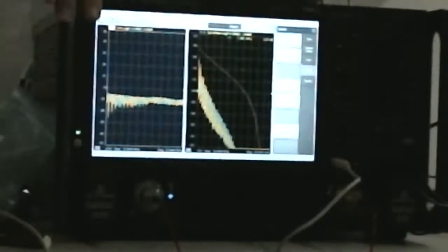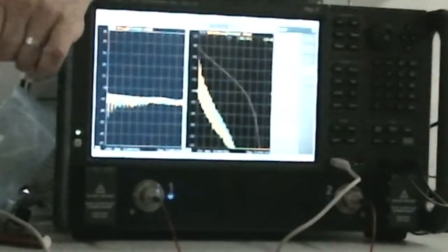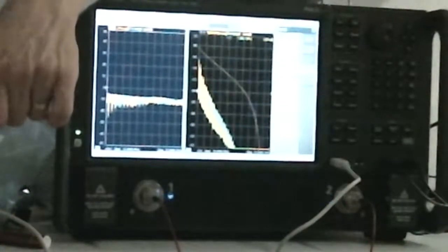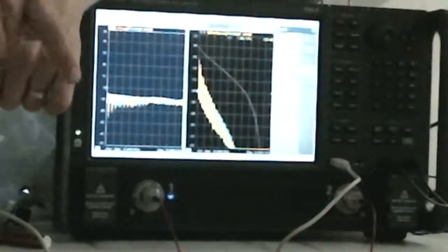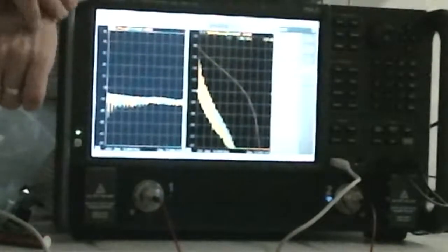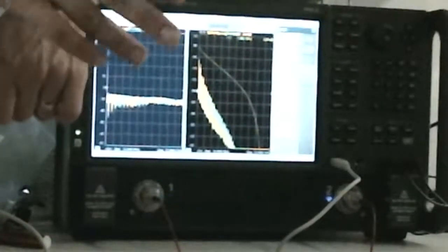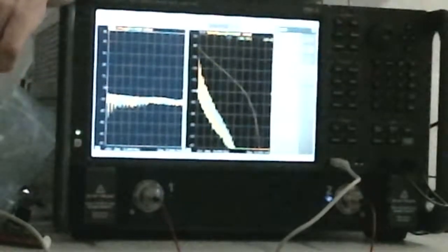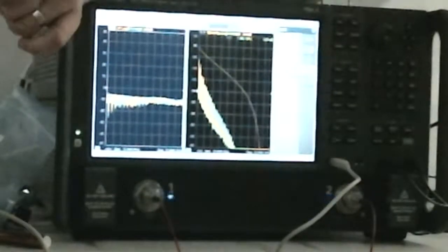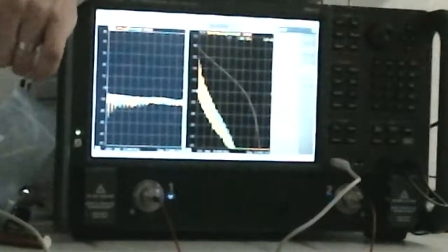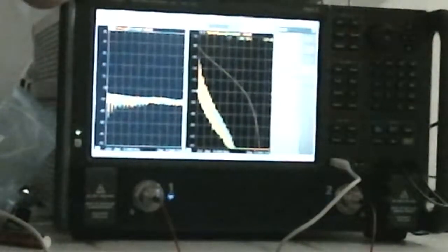This is not on a network, the machine. I don't think this machine is on a network right now, right? No, it's not. It can be, and then from there you can actually update the firmware directly on the instrument. It'll download it if you put it on a network. There's something in here that says update firmware. It'll download the firmware and then say, okay, closing all measurements. Are you ready to install? And it'll do all of that. Some people don't like to put their machine on the network because of IT security policies. It's entirely up to you guys how that works within York.